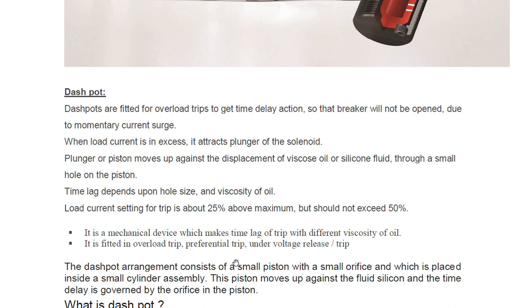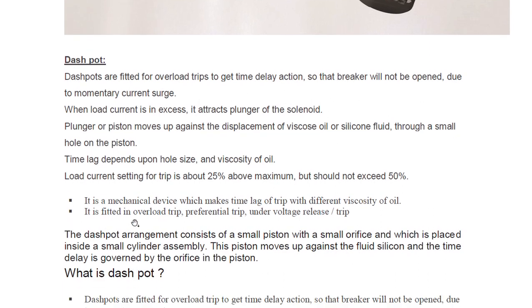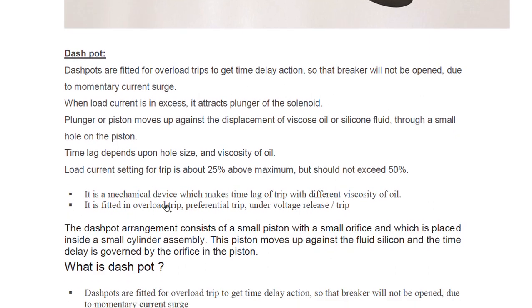Load current setting for trip is about 25 percent above maximum but should not exceed 50 percent. In a nutshell, it is a mechanical device which creates a time lag for the trip using different viscosities of oil. It is fitted in overload trip, preferential trip, under-voltage release trip.